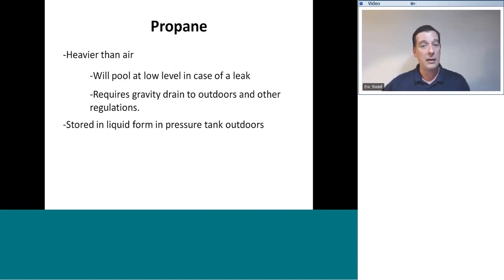If you're on the eastern seaboard or in New England, where a lot of traditionally oil-fired equipment is being converted to propane to avoid the high cost of fuel oil in some cases, look for that as well. There's a good chance that it may not have been added in, and a lot of those homes have dug basements, so check for that and offer to upgrade. And check with your local wholesaler, ask them if they have propane safety shutdown devices, and I'm sure they'll be more than happy to tell you all about them.